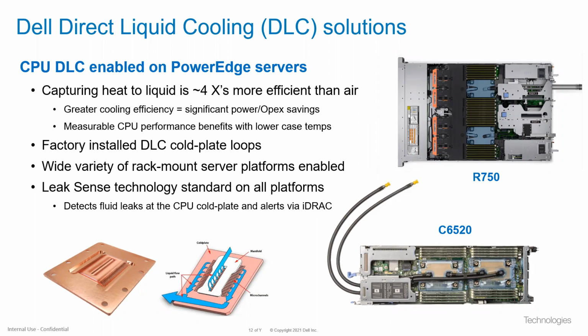One new capability with our 15G DLC solution is leak sense. What that does is detects if there's any condensation or coolant leak at the CPU. The leak will be detected by a board that's under the cover of the cold plate loop. It's best seen in the picture to the lower right. It's sort of a beige color, as you can see under the translucent plastic cover of the cold plate loop. And that would send a signal when it detects any drips to our software management, our iDRAC software management capability.